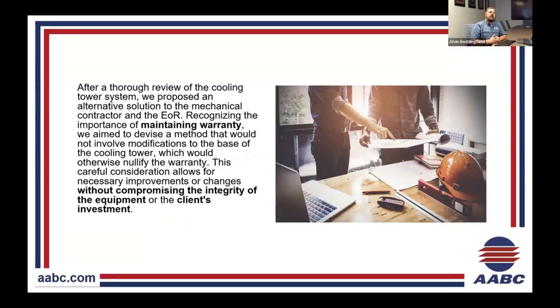So after our review and talking with the engineer of record and the mechanical contractor alongside the mechanical equipment supplier, the importance of this was to maintain the warranty of the equipment. And when we talked with this equipment provider, they said if anything was cut, any hole was repenetrated into that basin, it would void the warranty. And that's the one thing we didn't want to do for the district, was to void any warranty that new equipment would be provided, because new equipment, they'll have a 5-year warranty.